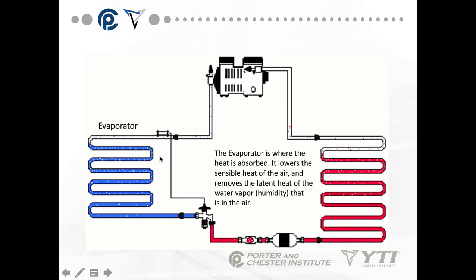If the air surrounding it is 80 degrees, my boiling point might be at 32 or 35 degrees. We want 35 degrees in air conditioning so we don't freeze anything. When a substance boils off — like a liquid refrigerant — it takes heat to make it boil. That heat is absorbed from the air blowing across the evaporator coil and gets transferred into what becomes a vapor refrigerant coming out of the evaporator.